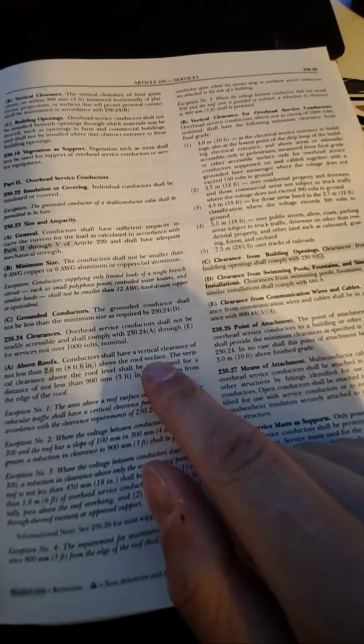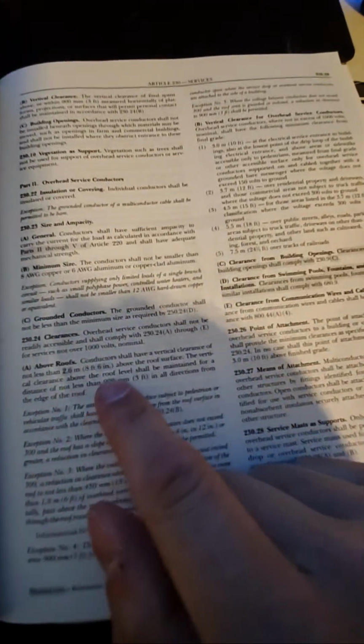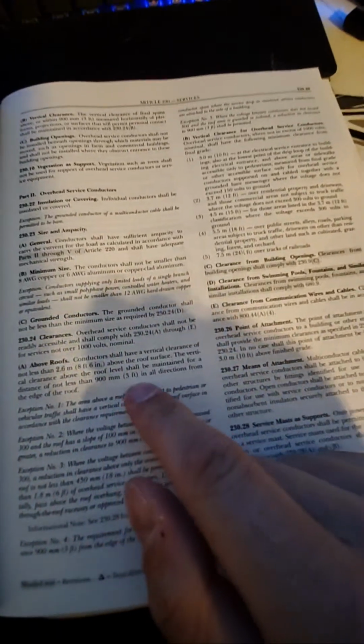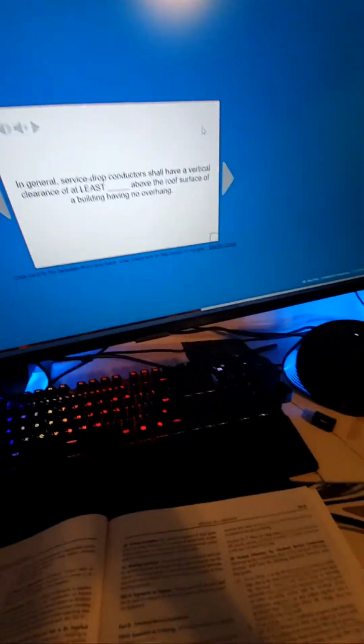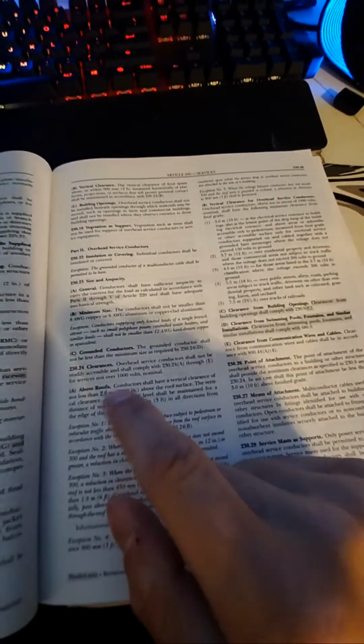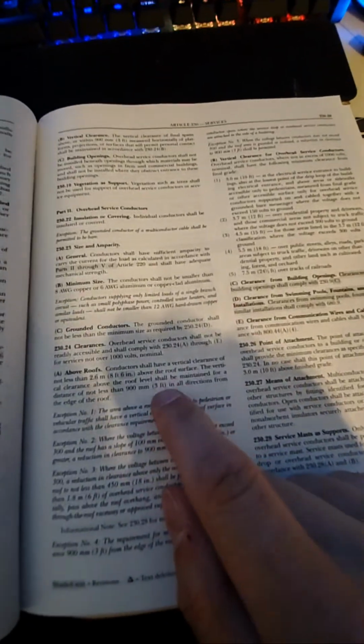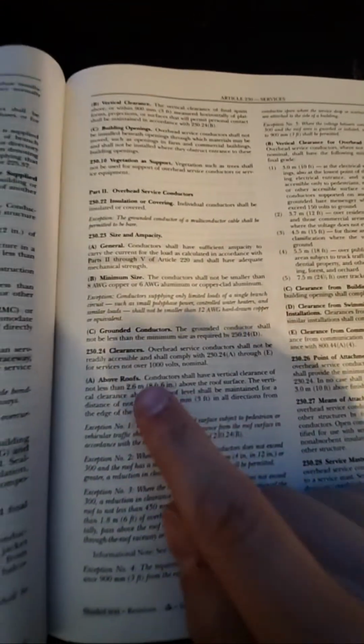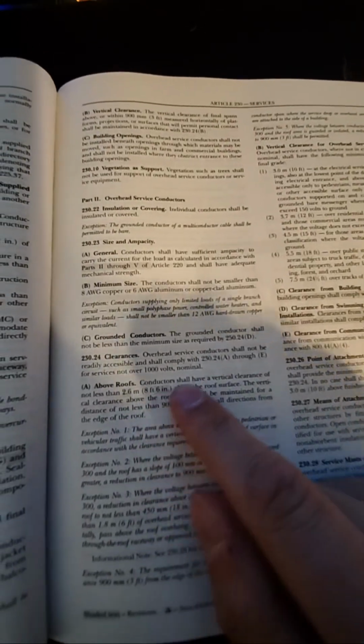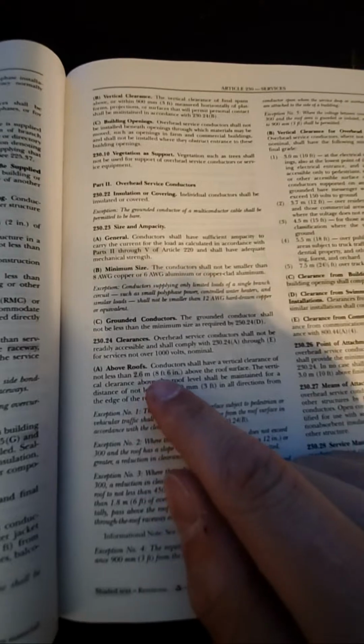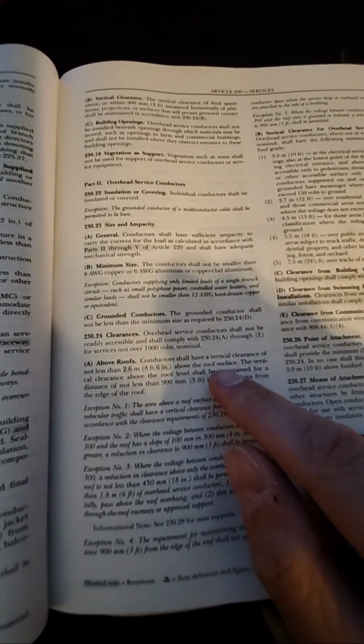Go here, above roofs, conductors shall have a vertical clearance of not less than 8 foot 6 inches above the roof surface. The vertical clearance above the roof level shall be maintained for a distance not less than 3 feet in all directions. So it's a vertical clearance. Vertical clearance of not less than 8 foot 6 inches. I actually would have got that one wrong, man. I would have jumped to 3 feet, because that's typically what you see. So they want a vertical clearance of not less than 8 foot 6 inches above the roof surface. So there you go. If we click here, it's probably going to be 8 foot 6.